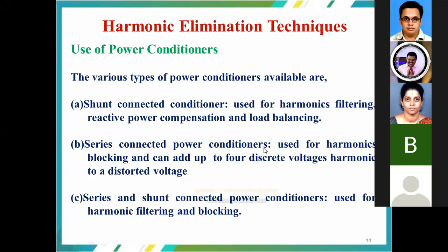And use of power conditioners: shunt connected conditioners, series connected conditioners, or series and shunt connected power conditioners. So these power conditioners are going to give a negative impact to the generated harmonics, or they generate the negative signal, and thereby take care of the harmonics as well as the reactive power compensation.